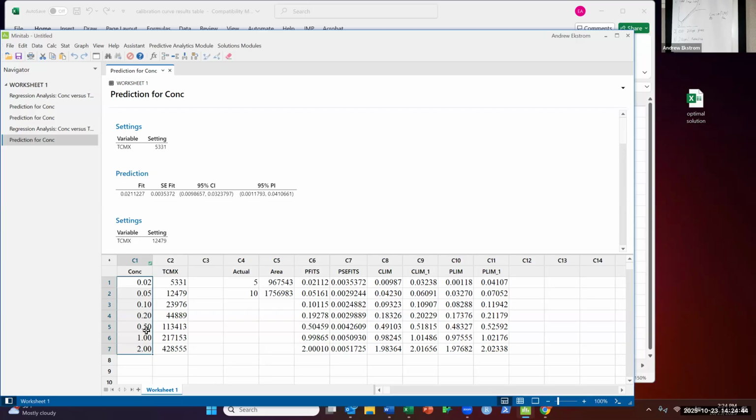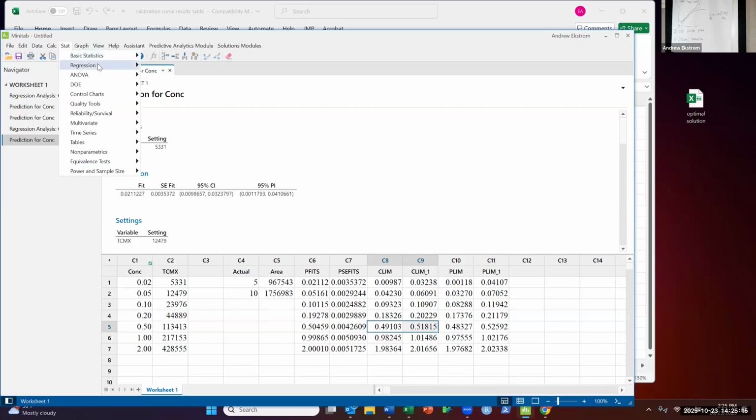With this one, you put that 50-pound weight on the scale, it's going to tell you that comes out to be 50.5 pounds, and it's going to be somewhere between 49.1 and 51.8 pounds, which for what we're trying to do here is acceptable. Nothing's being overestimated, nothing's being underestimated. If we look at these last two data points, just to see what they do.